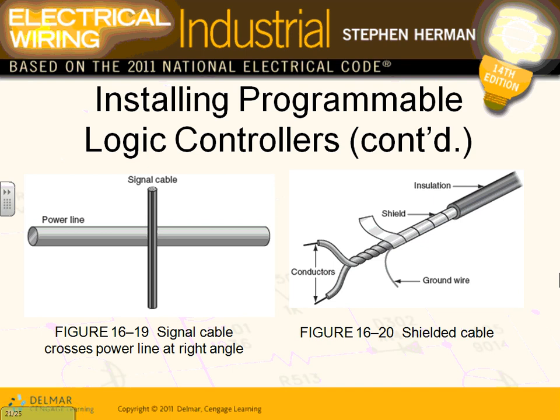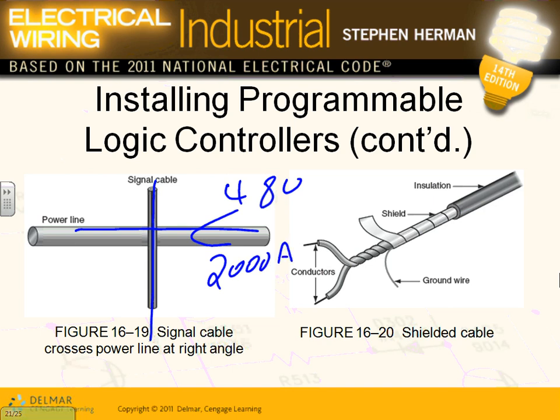Shielded. When you cross a power line, they always tell you to cross them at a right angle like this, so you don't have magnetic interference. By the way, if this is a 480 volt cable carrying 2000 amps, that's where you guys come in. And I have a signal cable right next to it. I, as an owner of a 2000 amp 480 cable, care less about your signal. Your signal is not going to affect my 2000 amp 480 cable. But this amount of magnetic field from the current could induce voltage and current into this signal cable that will be interpreted as 5 volts at the end of that cable, whatever voltage, and could give a false signal.